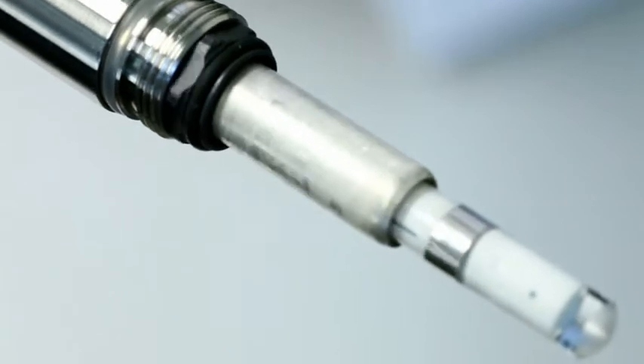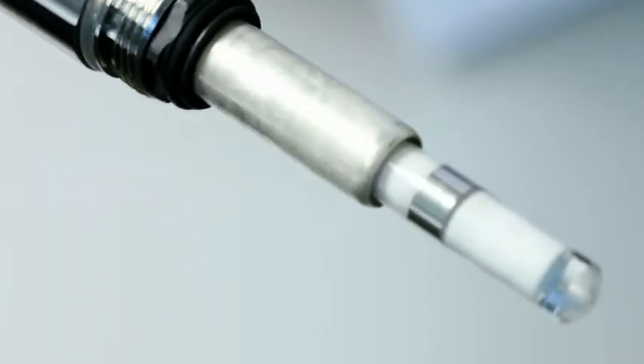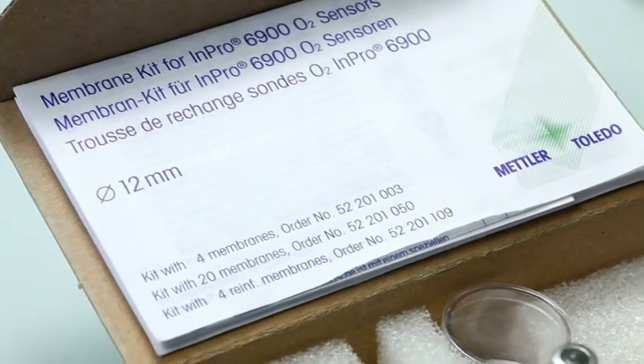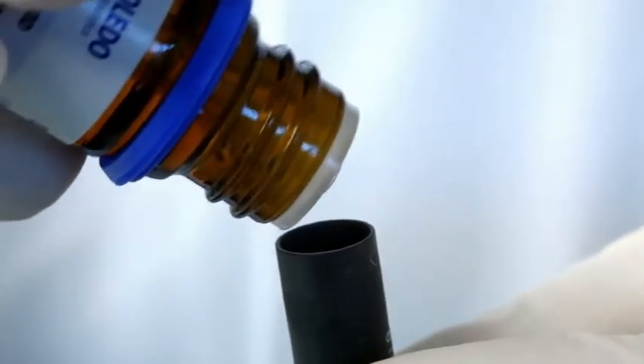New o-rings for each type of gas sensor can be found in the membrane replacement kit. Take a new membrane body from the replacement kit and half fill the cavity with the electrolyte, which is also part of the kit.